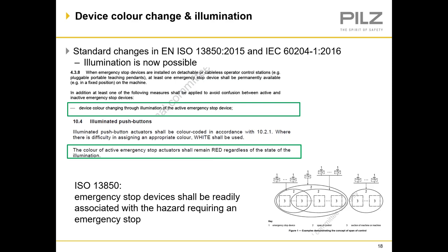At least one of the following measures shall be applied to avoid confusion between active and inactive emergency stop devices: device colour changing through illumination of the active emergency stop device. Section 10.4 of IEC 60204 part 1 covers illuminated push buttons — illuminated push button actuators shall be colour coded in accordance with section 10.2.1; where there is difficulty in assigning an appropriate colour, white shall be used. The colour of an active emergency stop actuator shall remain red regardless of the state of illumination — this means you do not flash the red part.